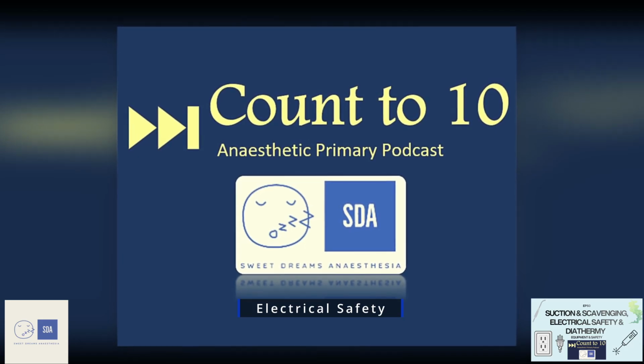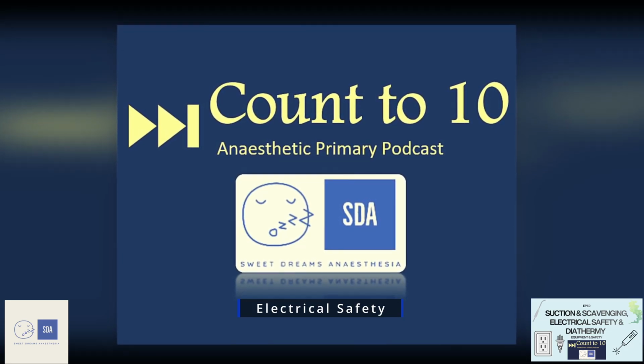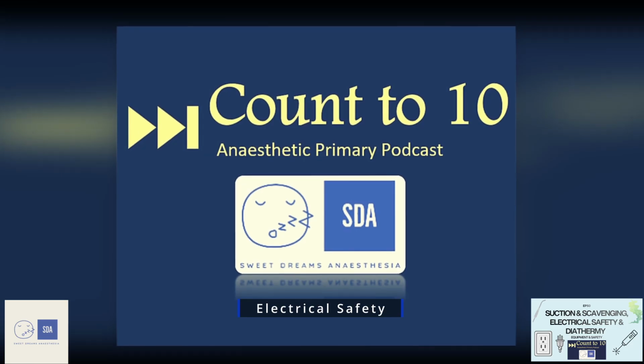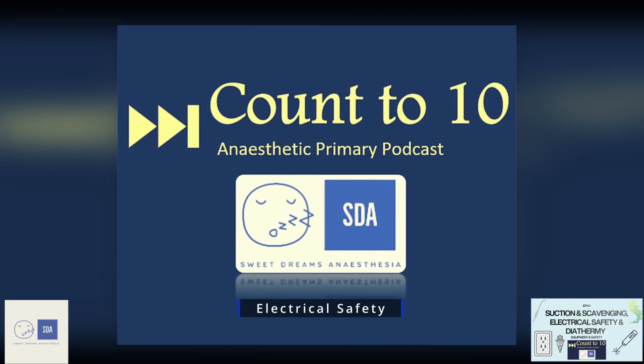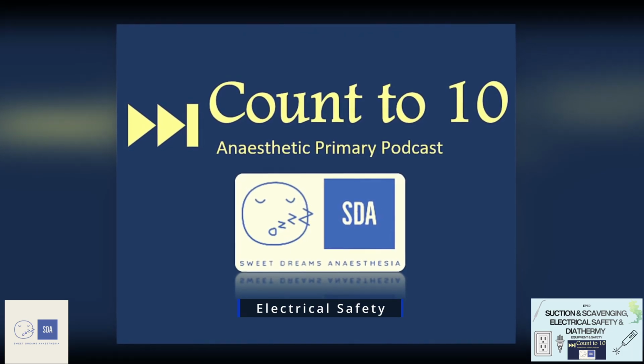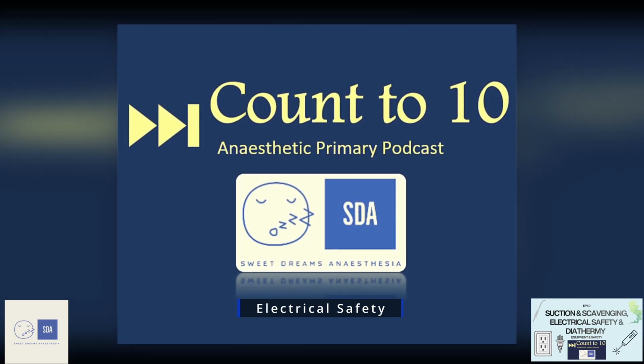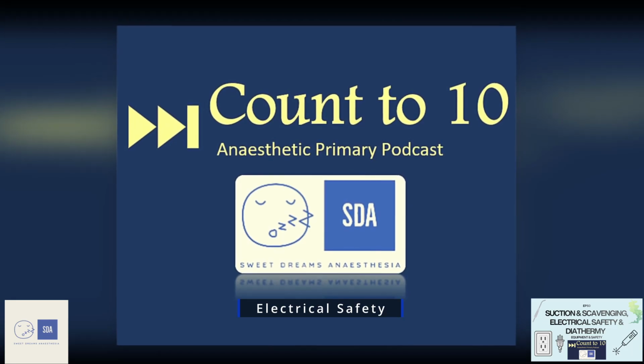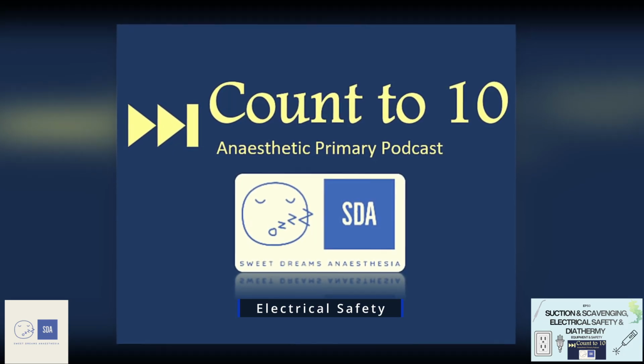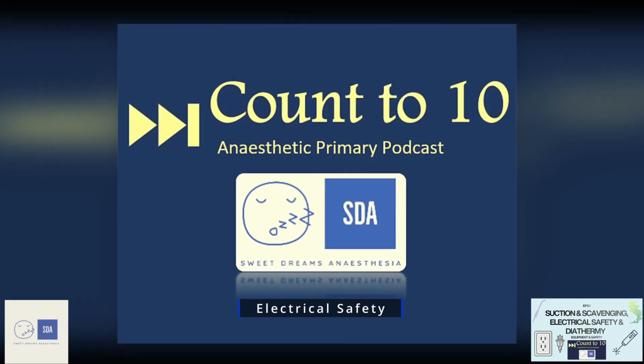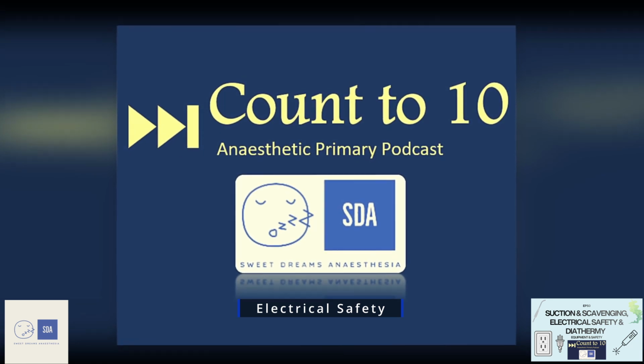When we talk about electrical supply to the operating theatre, what we have is the power supply coming from the power stations at very high voltages in the multiple hundreds of kilovolts that reaches the power points we see in our operating theatre. At these power points, the voltage here is 240 volts, and it's been decreased from those high numbers through a series of step-down transformers. And this output supplies electricity at 50 Hz at an alternating current, and the reason we use an alternating current is because it's just more efficient compared to a direct current.